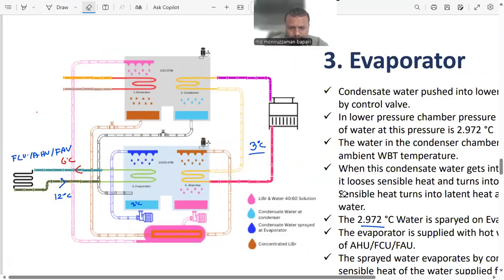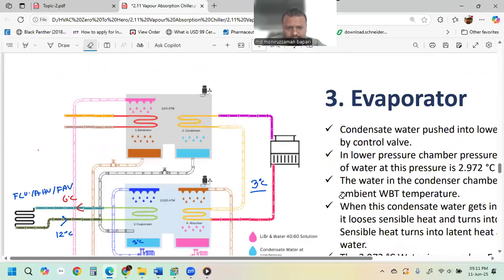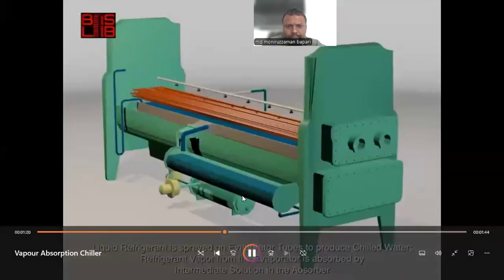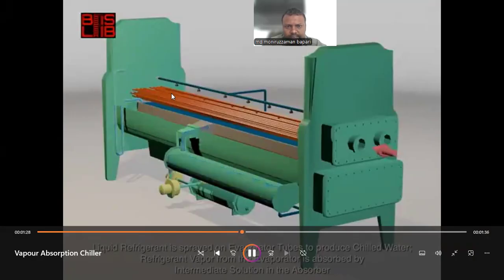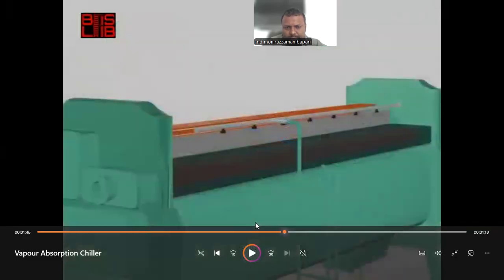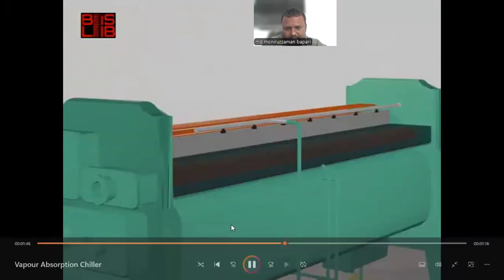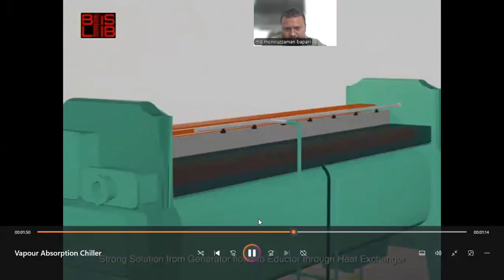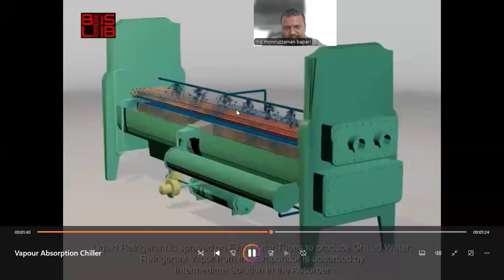Okay, now let's go to the animation once again. Now water is being sprayed. This is step 3, evaporation. So water is being sprayed, and here we have hot water coming from the fan coil unit or air handling unit. As it is being sprayed, remember inside here in the lower pressure chamber, the pressure is 0.001 atmospheric pressure. So the boiling point here is around 3 degrees centigrade. So now we have vapor in here. So vaporization happens, evaporation happens.